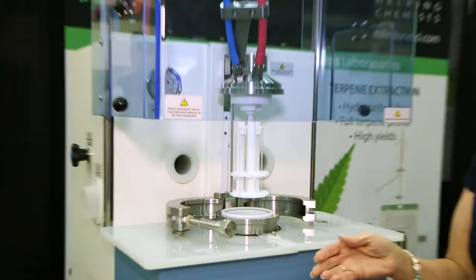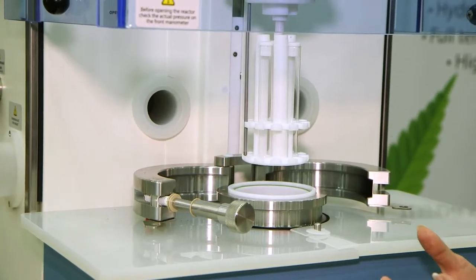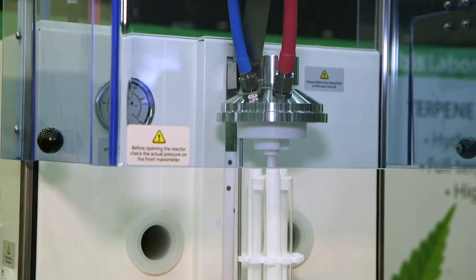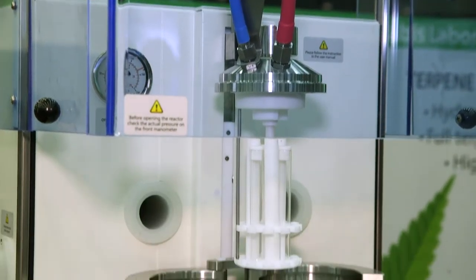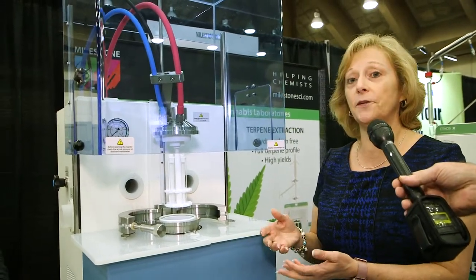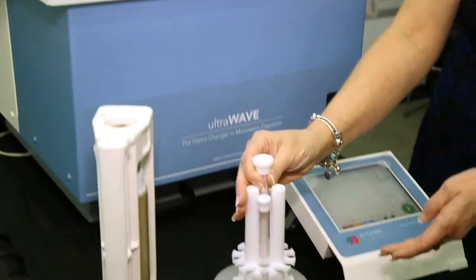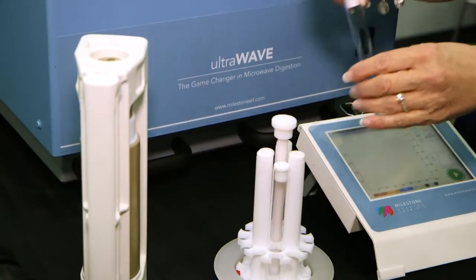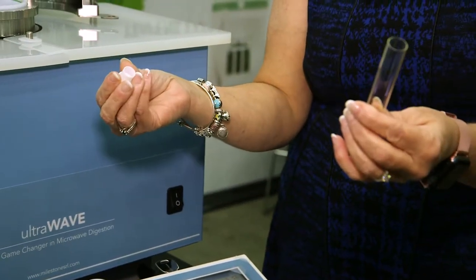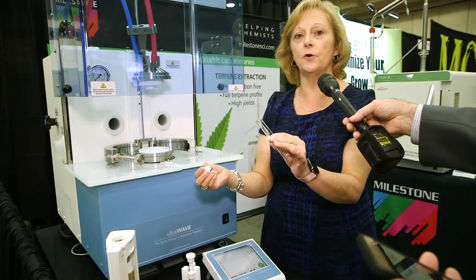That is then lowered into the single reaction chamber vessel, which is pressurized to keep all of the volatile elements sealed within those loose-fitting capped vials. The digestion procedure takes place right there. When the digestion is finished, all you have to do is, in reverse order, take the vials out, uncap, and pour the contents into your auto-sampler vial.